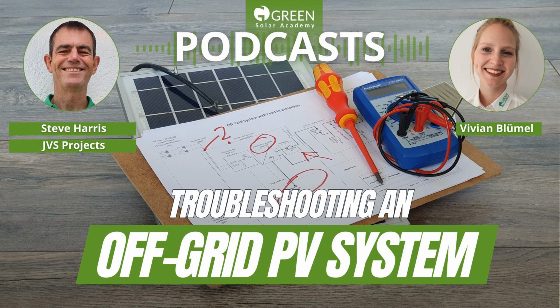If you're dealing with lithium-ion batteries, read the little handbook. There's a little reset. Lithium-ion batteries will very often switch off because they've been incorrectly sized for the system and the loads that come off the system. Pylon Tech are a very common, very popular brand of battery. They have very stringent discharge parameters. So if there are not enough batteries in the bank for the inverter, it's very easy to switch off Pylon batteries and think your system's gone down, and all it needs is to reset the batteries. We've seen that many times. So understand what components you've got.